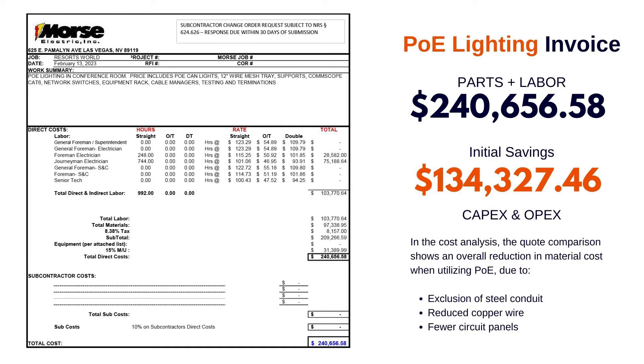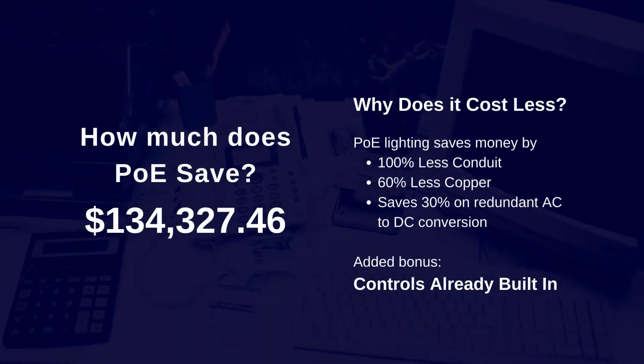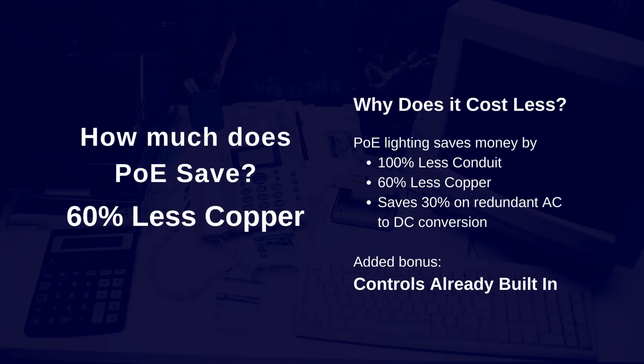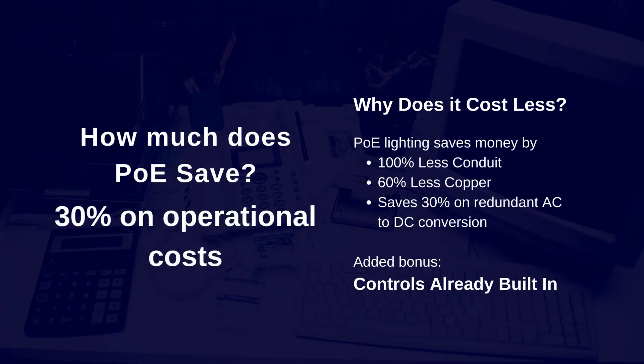That's close to 50% savings over what Resorts World would have expected to spend. POE actually saves on installation costs by removing the need for conduit. Low voltage lighting systems use 60% less copper and save 30% on operational expenditures by eliminating inefficient AC to DC conversion at each light. Best of all, the Denton DBI POE solution has controls built in, so there is no need to procure another $100,000 lighting control system.